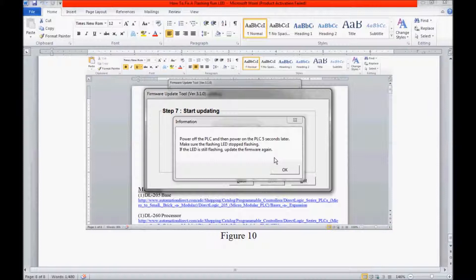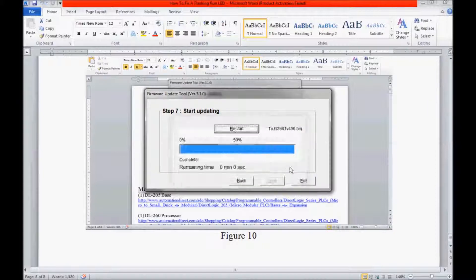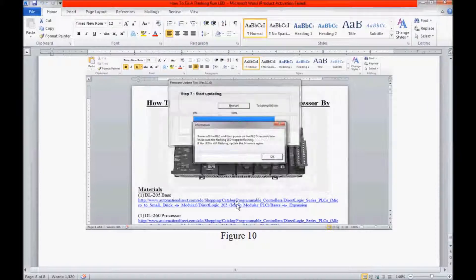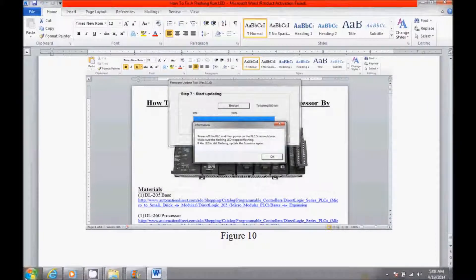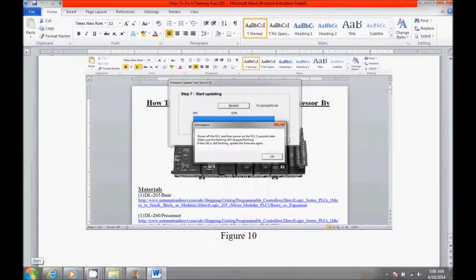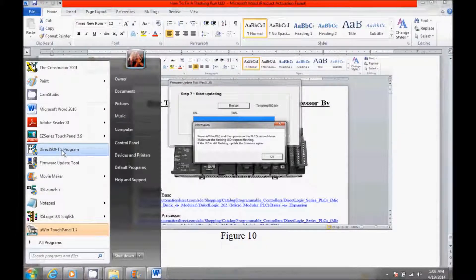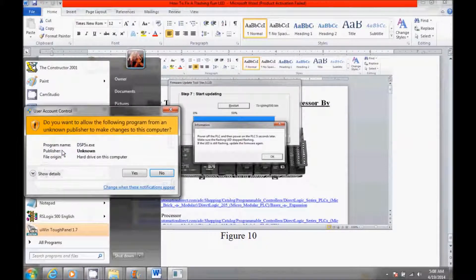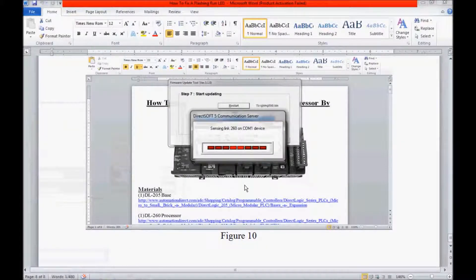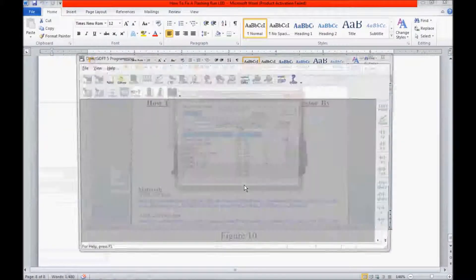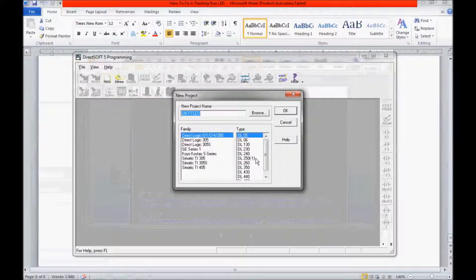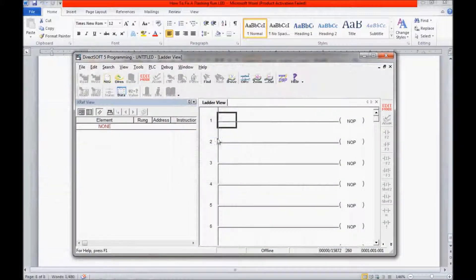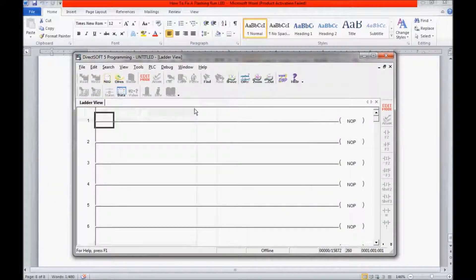Okay, since my RunLight has stopped flashing, I am going to check this out and make sure that it runs. So I am going to exit this. I am going to pull up DirectSoft 5 program and attempt to communicate with it and download a small program to it.